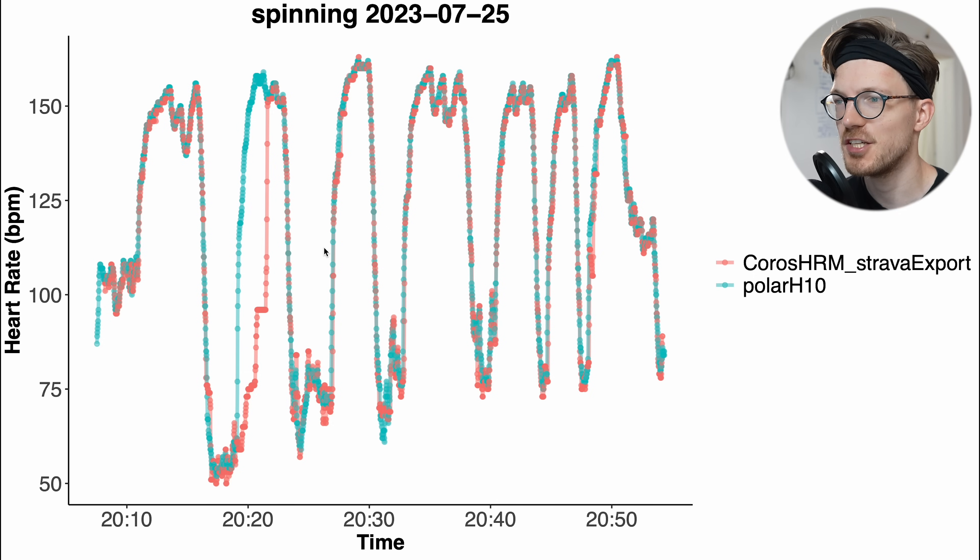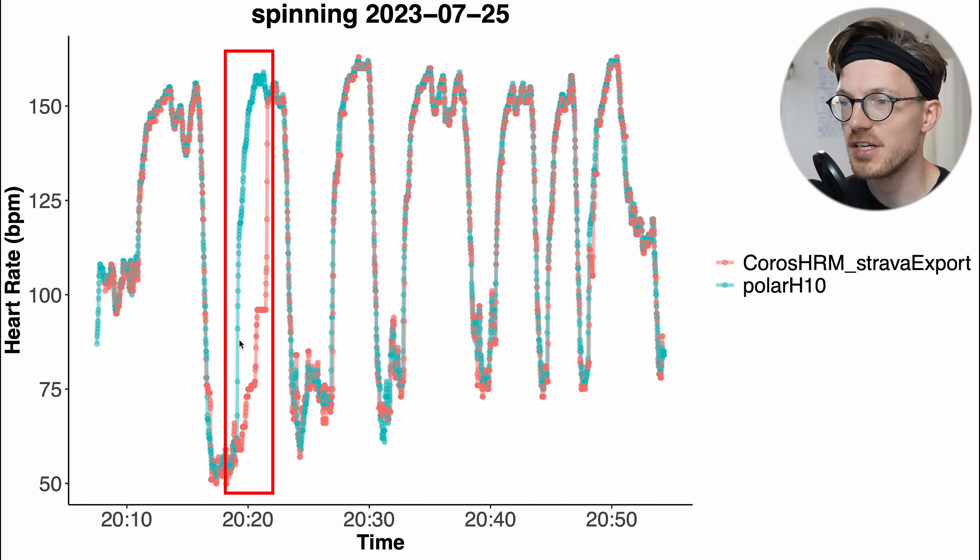Here we have the results for that spinning session. Again, in blue-green we have the ECG chest strap, and in red the Coros heart rate monitor. In most cases there's an almost perfect overlap between the red and blue lines, indicating perfect agreement between those devices in those moments. But there's one moment where the heart rate monitor detected a too-low heart rate — this is likely the moment where it detected half the actual heart rate.